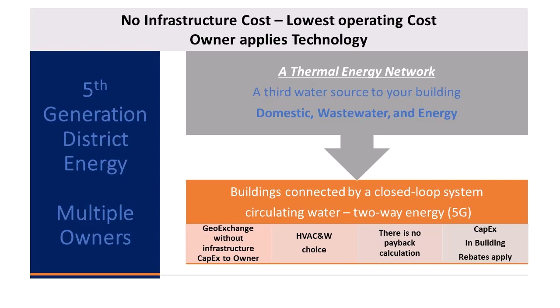They didn't have to net each other out inside a condensing unit, they netted each other out on the whole building. That logic is still something we want to talk about, except the advantage today is, based on the slide I showed you previously, you don't have to have a bunch of little bitty units all over the place. That same logic of operating for efficiency, a compressor in a controlled range can give you hot and cold water at the same time, can be a package unit to VAV, to DOAS, to sewer heat recovery, to your pond, whatever. All of those things are possible.